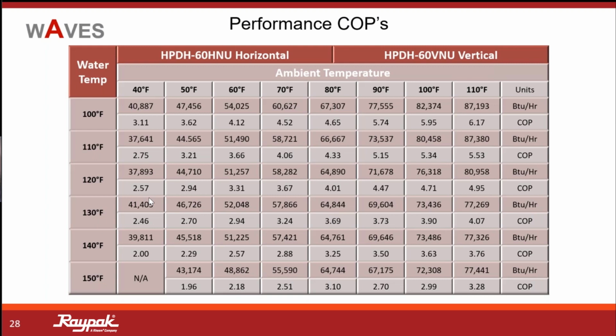There is a message. And the message has to do with your supply water temperature, let's say 110 degrees, right? That's the temperature of the water, over here on my vertical axis, 150 degrees, 140, 130. Here's my water temp axis right here. And here's my ambient air axis over here. So if I'm in a region where I have the availability of 100 degrees Fahrenheit of ambient air, and I have a supply temperature of 140, I quickly do the math and I can say, look, I'm going to get into this range of COPs. And COP is nothing more than coefficient of performance.